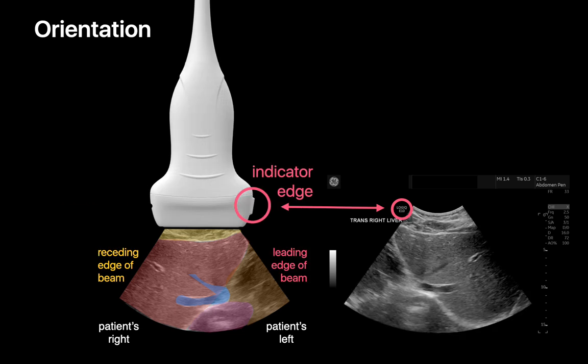Let's say you were to flip the probe 180 degrees so that the probe's indicator edge faces the other direction. While the image displayed on screen would also flip, the indicator mark on the displayed image remains in the same spot, since indicator marks are static graphics that are usually not intelligent about the way you're holding the probe.